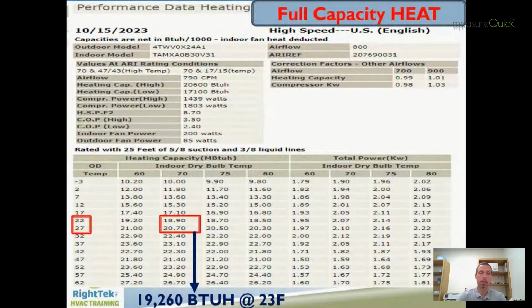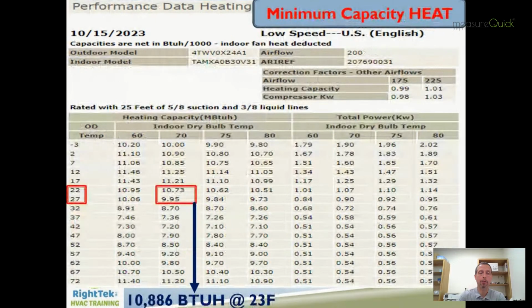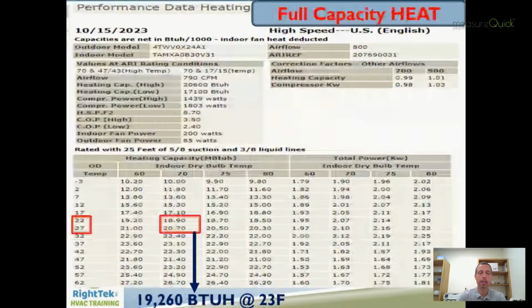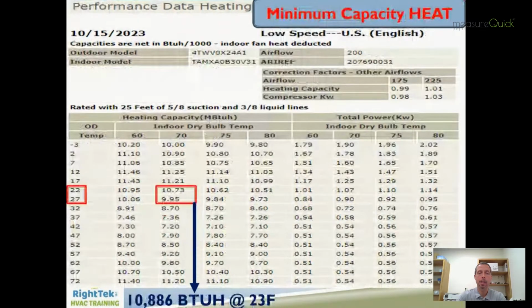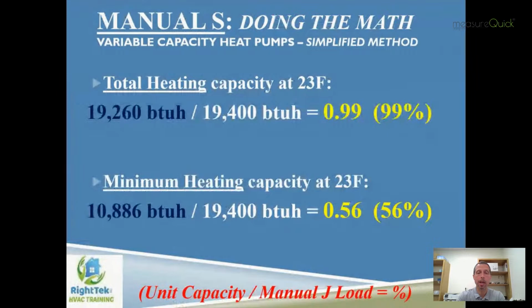So again, we're just going to go into our performance data. I'm showing you here full capacity from a major OEM on one of their variable capacity heat pump systems. And I'll look at it again at minimum capacity here. And again, minimum capacity for heating. So I get my two numbers based off of this. And again, I basically apply the same math logic that we've been looking at before. And in this particular example, which I'm applying to the same house, you'll see that that heat pump is only meeting 99% of the load. And it asks for 1.0 or 100% of the load.